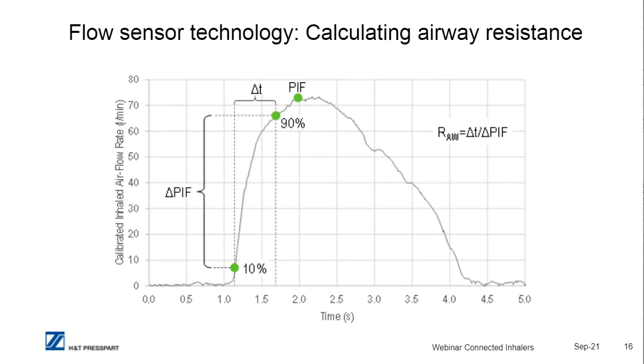But before, another parameter I would like to show, which is possible with the integration of such a flow sensor, because here a calculation of the airway resistance is performed. And the airway resistance is defined by the ratio of the time needed to increase the flow rate from 10 to 90% of the peak inspiratory flow rate, divided by the value of the peak inspiratory flow rate. In simple terms, it just gives us an indication of how severely restricted the airways are.